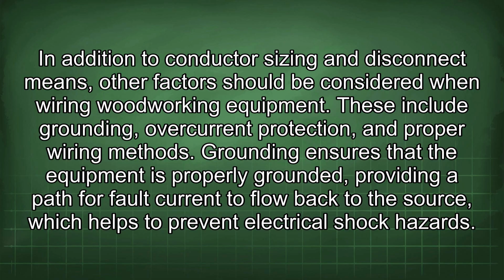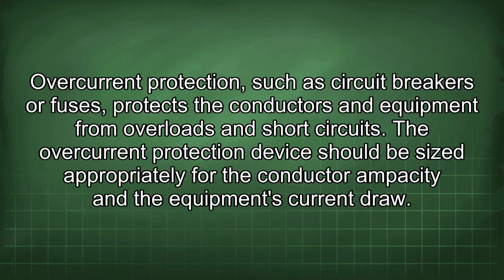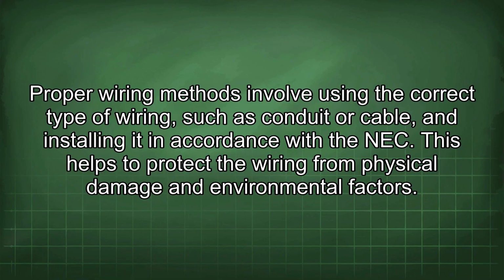Grounding ensures that the equipment is properly grounded, providing a path for fault current to flow back to the source, which helps to prevent electrical shock hazards. Overcurrent protection, such as circuit breakers or fuses, protects the conductors and equipment from overloads and short circuits. The overcurrent protection device should be sized appropriately for the conductor ampacity and the equipment's current draw. Proper wiring methods involve using the correct type of wiring, such as conduit or cable, and installing it in accordance with the NEC. This helps to protect the wiring from physical damage and environmental factors.